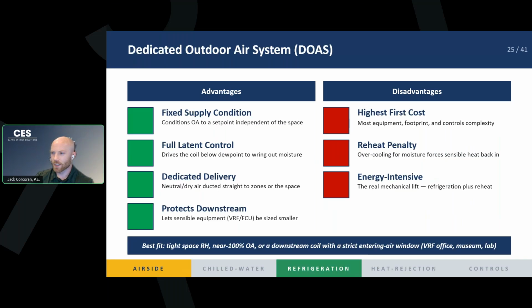And lastly, our DOAS, right? We have an extra green box on this screen because DOAS have a lot of advantages, right? We're going to be able to hit any supply condition that we want, right? We can size our coil to deliver that subcooled, dehumidified air, and we can reheat it back up. It's great. You can pick your controls to be whatever discharge temperature and humidity you want. You get full latent control.